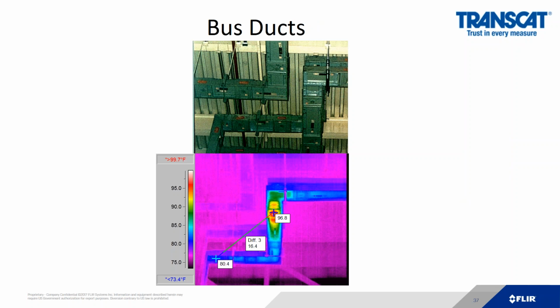Many applications and many facilities can be also looked at, like bus ducts. This is what we would call an indirect temperature measurement. There's heating on one part of the bus duct versus the other side of it. That's 16 degrees. Anecdotal evidence tells us that that rise is probably 20 times that temperature difference. And when that part fails, if you are familiar with bus duct fires, you know they can be quite explosive.